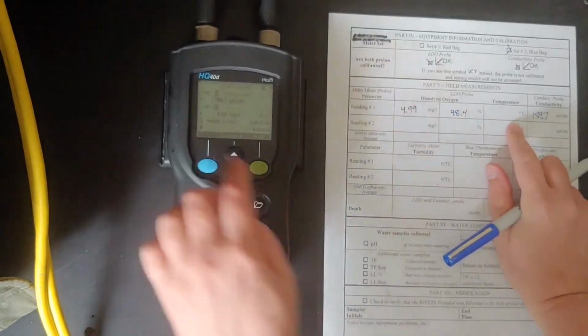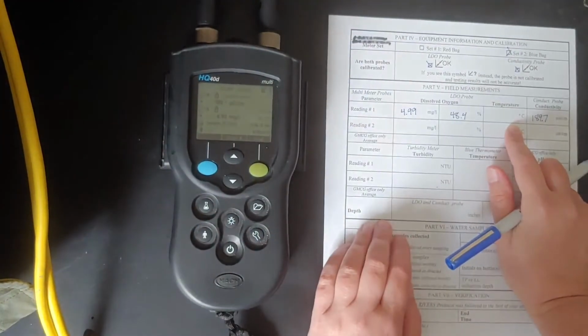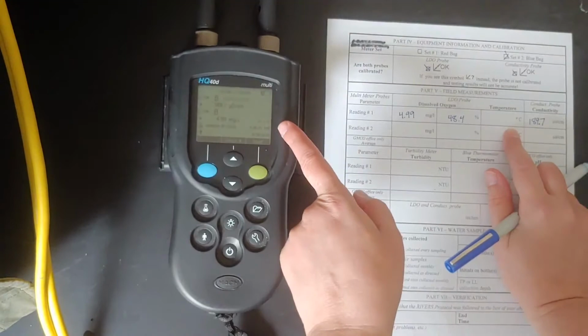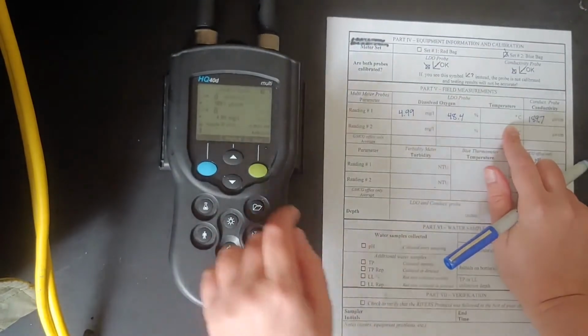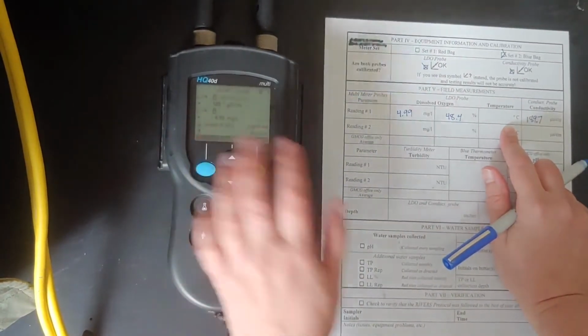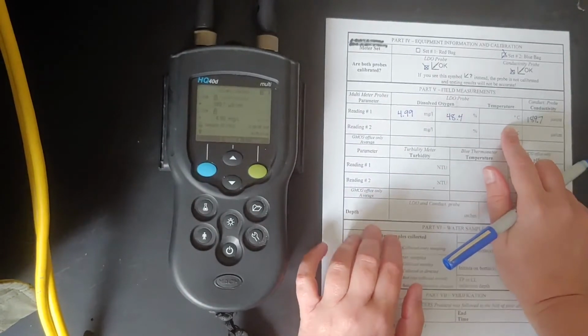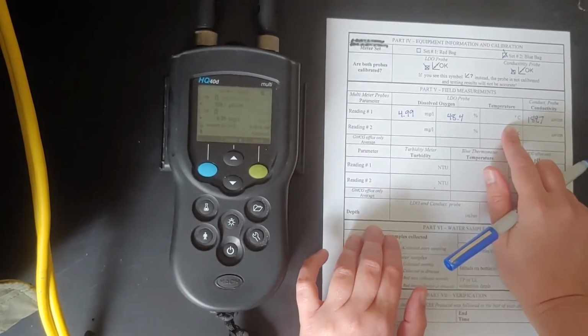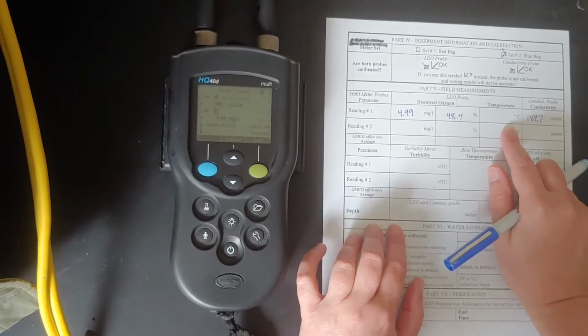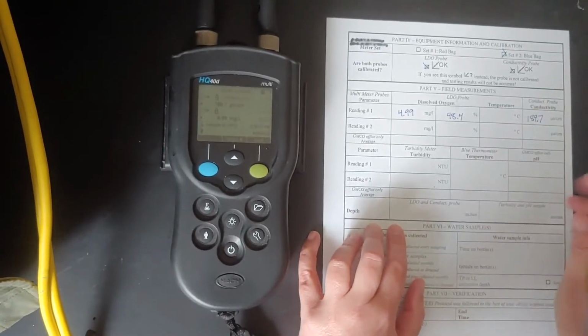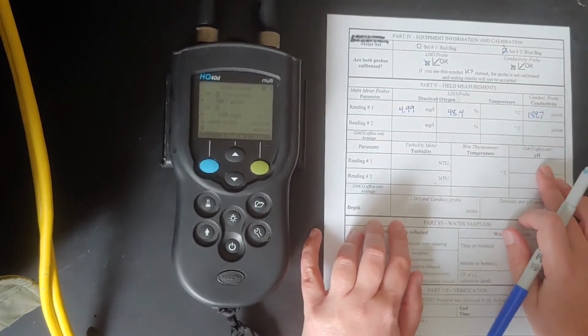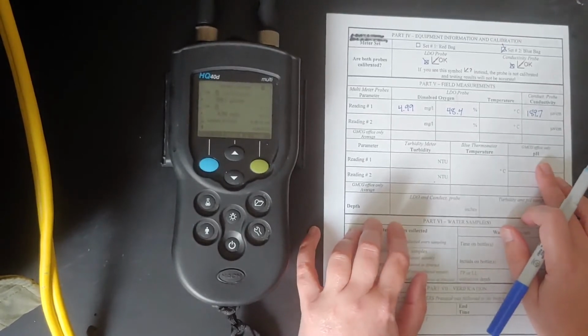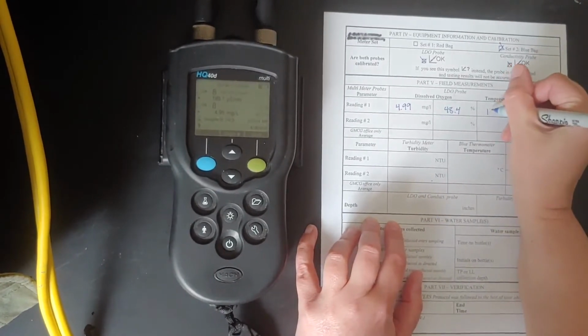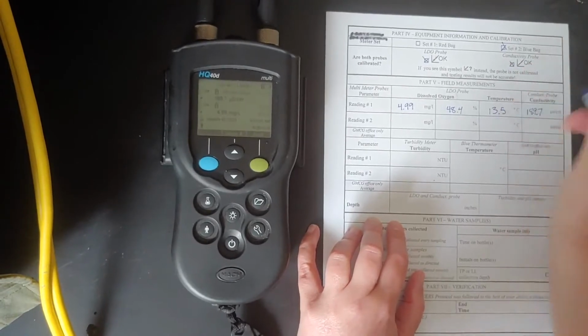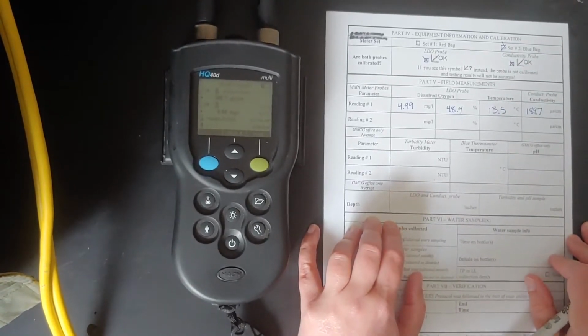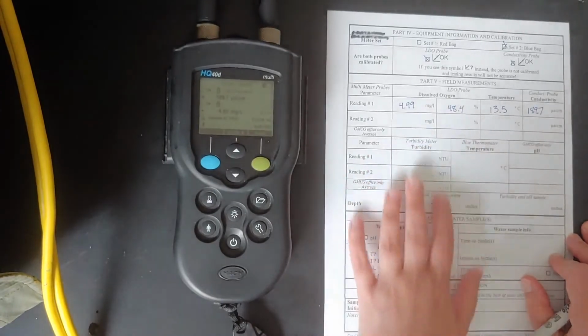And finally, I'm going to take the temperature from the dissolved oxygen probe. Now, both probes do provide you with a temperature reading, but for official recording, we're going to take the dissolved oxygen probe. That being said, if for some reason you feel the temperature is off from your dissolved oxygen probe, please record the one from the conductivity probe. You will also be given a blue thermometer to put in at your site that can be used for comparison purposes. Once I've recorded my data, I'm going to hit the read button again and get my second set of parameters.